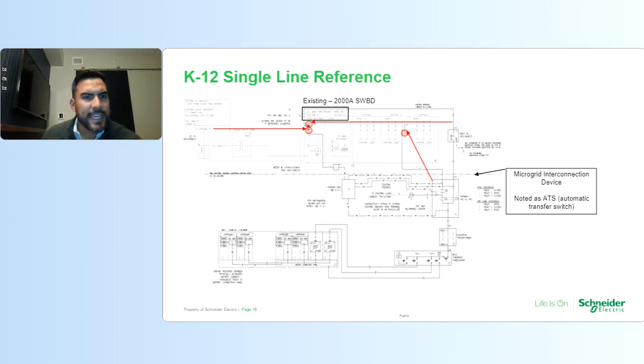So this is a K through 12 single line diagram I like to reference. This was in an existing facility for a school. And if you see here, there's an energy storage system, a 250 kW with about 1100 kilowatt hour energy rating, connected to a BESS combiner panel. And if you can see there to the right, just north of that combiner panel, there's a transformer, which is transforming it from a delta to a Y connection. And further to the right, there's a microgrid interconnection device.